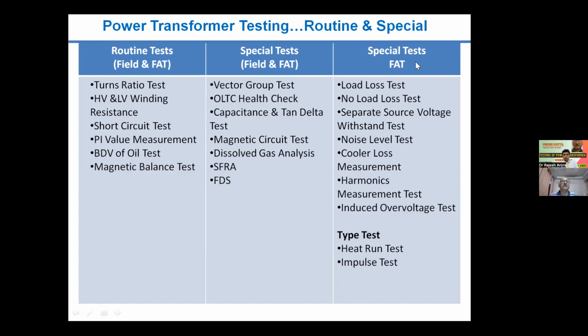So turn ratio test, HV and LV winding resistance test, short circuit test, PI value measurement, then oil testing, and magnetic balance test. In special tests, vector group test, OLTC health check, and to know the health of the insulation, we do capacitance and tan delta test of winding as well as bushings, then magnetic circuit test, then oil testing for dissolved gases, and some special tests like frequency response analysis and frequency domain spectroscopy. Though we will not be discussing the last two tests, SFRA and FDS, in detail in this session, we will discuss them sometime later on.